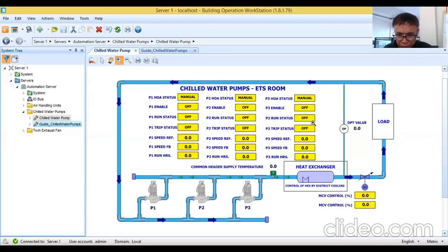1, 2, 3, 4. 4 times 3 is 12. So I need 12 digital inputs, meaning I will be needing a controller with 12 digital inputs. Then to provide some spare, maybe I can say, okay, at least I need a controller with 15 digital inputs.